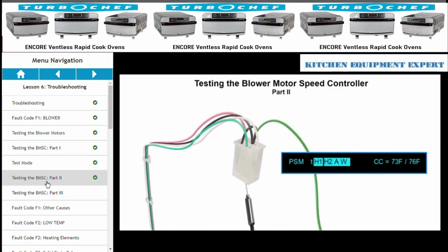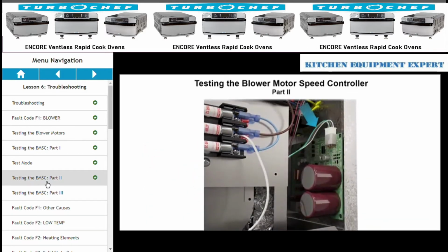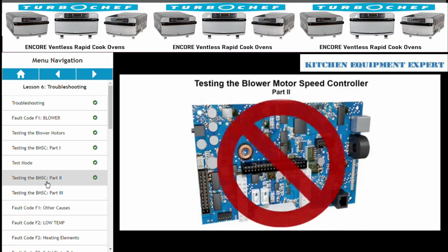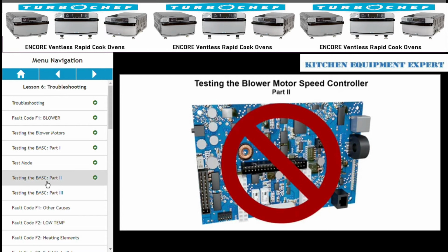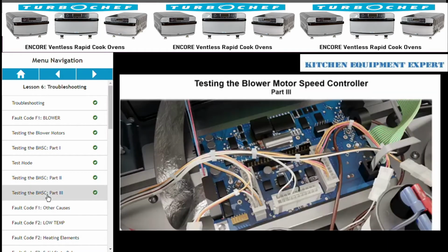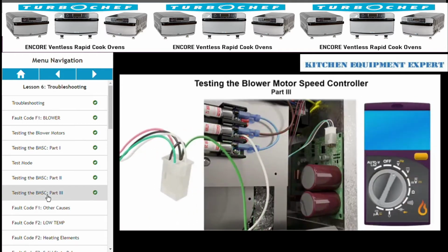Does the flashing backlight go away? If not, you need to check the wiring back to the board. If there are no breaks in the wire, and no loose pin connections, the main control board should be replaced. However, this time it does go away. Now, we need to see if we're getting voltage from the main control board. With pin 5 still grounded, and your multimeter set to DC volts, test between pins 1 and 2.